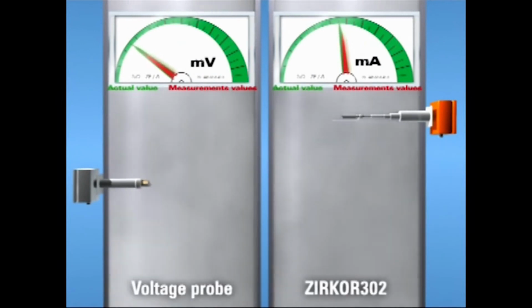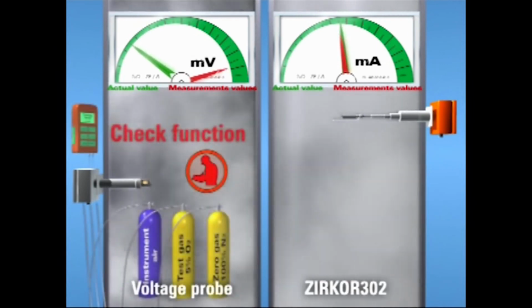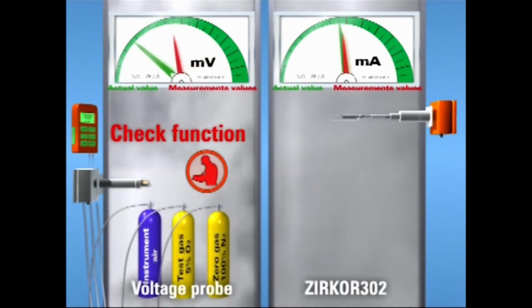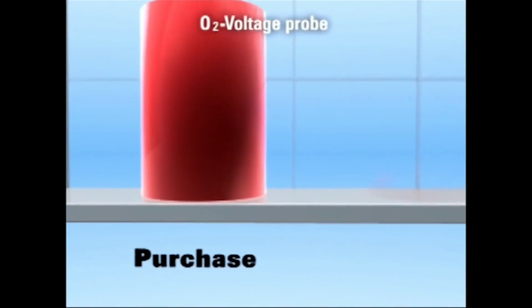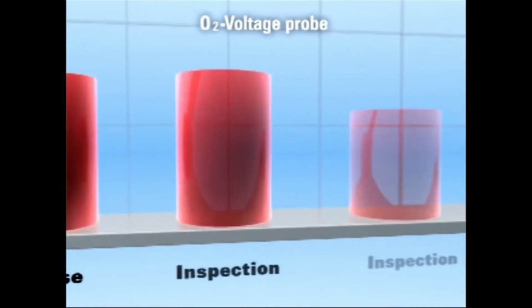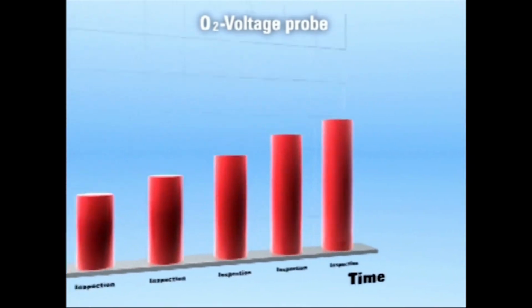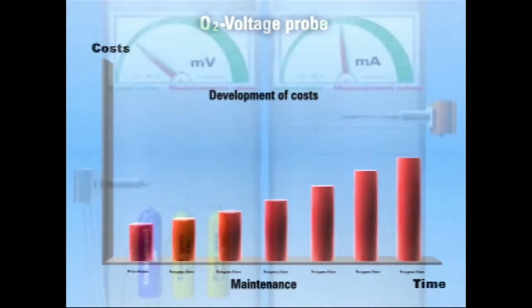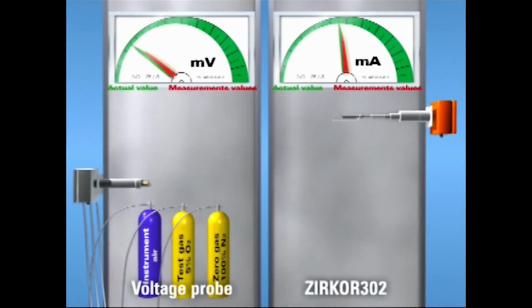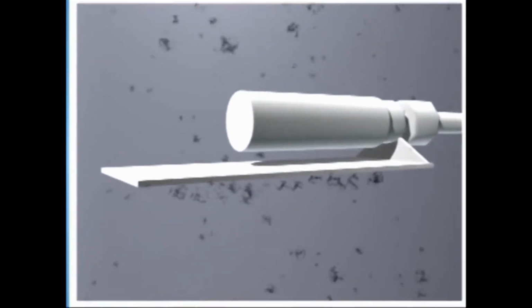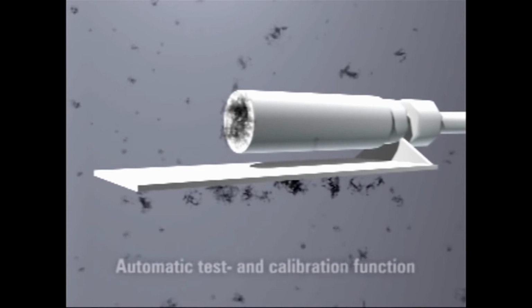The check function and the calibration of the voltage probe is carried out manually or semi-automatically with air and 2 different test gases. A fully automatic calibration is expensive due to the required test gas check. The test function and the calibration of the ZIRKOR302 are fully automatic and use ambient air only. Any equipment required for this task has been integrated in the device.